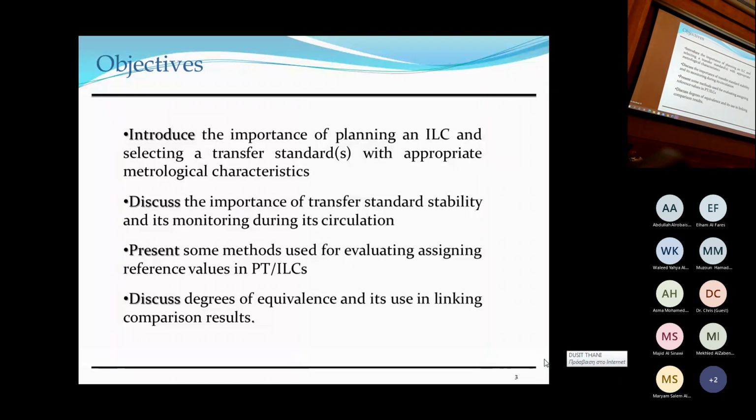Well, okay, it depends. We don't want to get into the details now of all of these things. But with regard to the uncertainty, I have to clarify that it's not a good idea to tell them which components they should be including. You should let them do it by themselves. They should give you their uncertainty budget, so you should tell them to give you the uncertainty components so you can judge whether they're on the right track or not. You should, in the protocol, have this request.